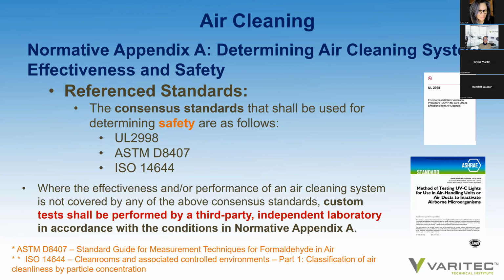For safety, in other words, will these technologies impact human health and well-being? They have to meet UL 2998 for ozone generation, which is that these air cleaning solutions cannot result in 5 parts per billion of ozone within the space. There's ASTM D8407, which measures formaldehyde, as well as 14644, which is for the classification of air cleanliness with regard to particle concentration. So these are the standards that normative Appendix A states that air cleaning technologies need to conform to.